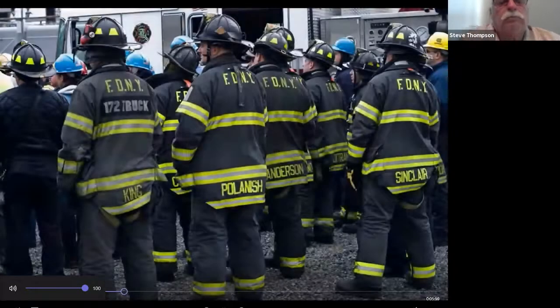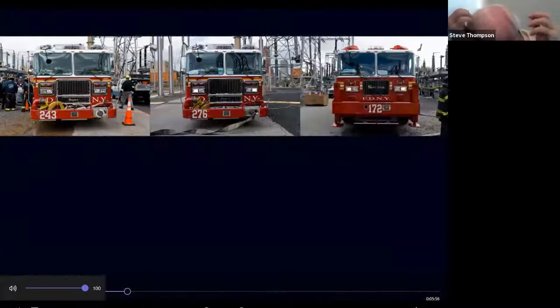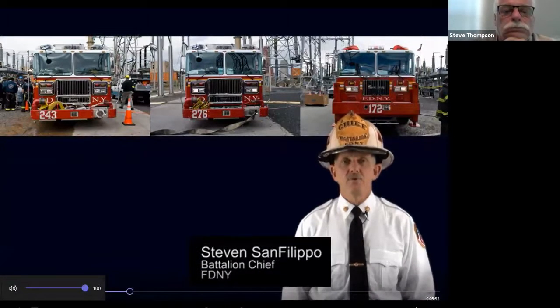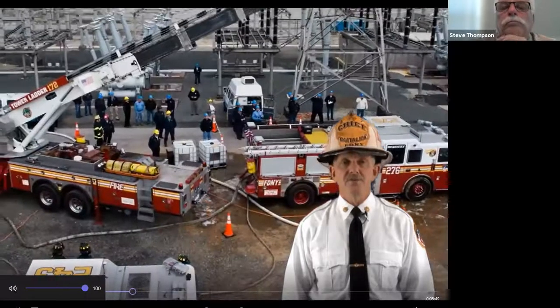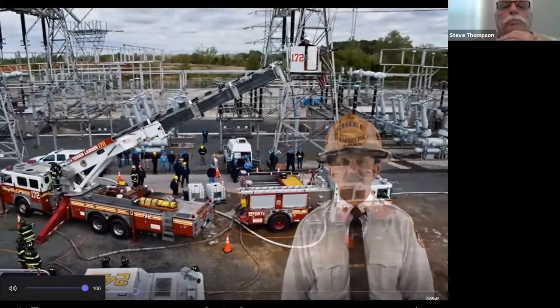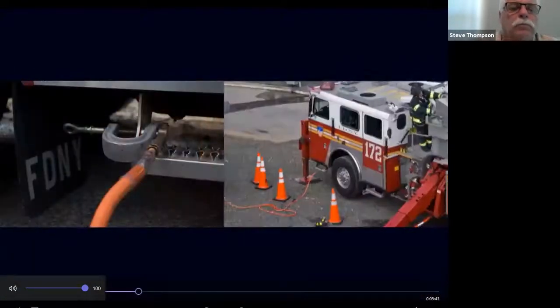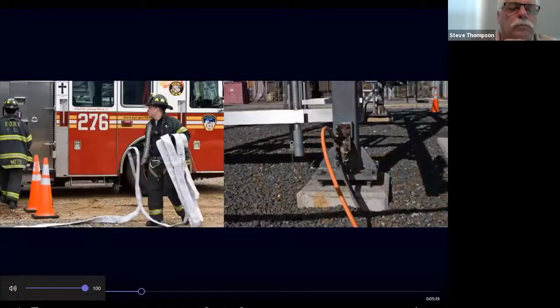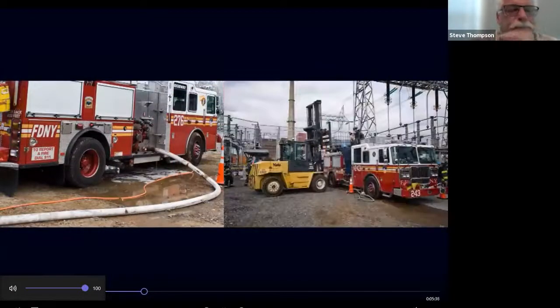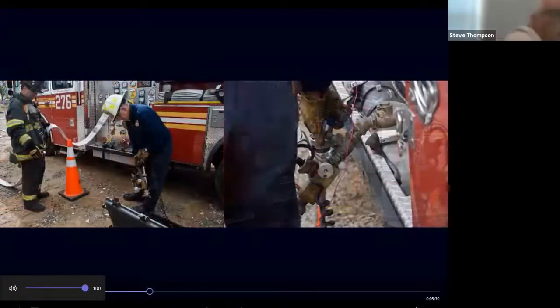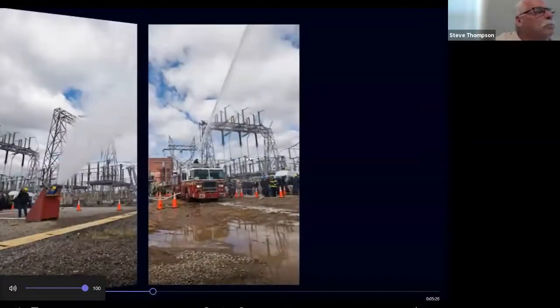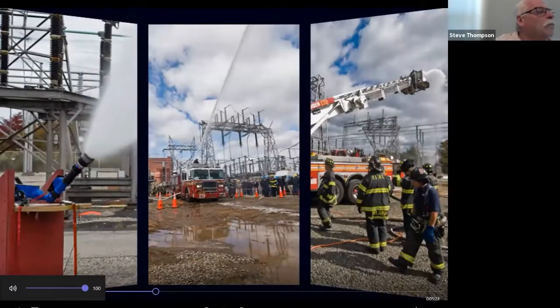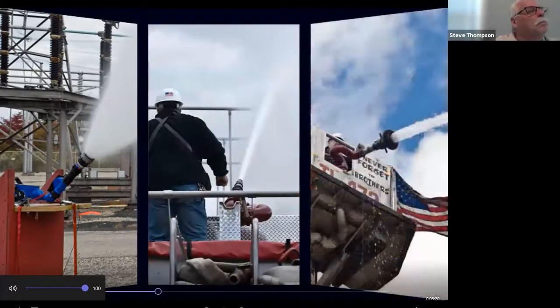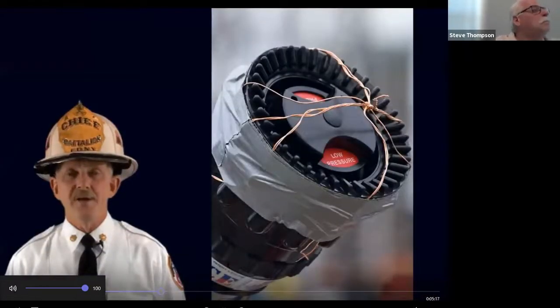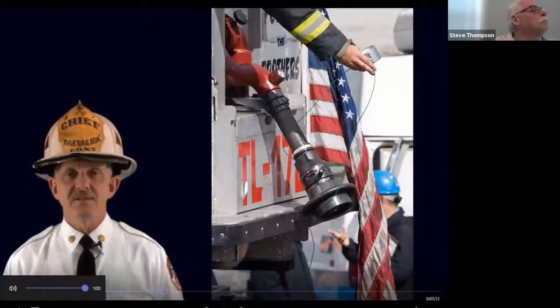For the Con Edison fire suppression test, the FDNY provided 2 pumpers and a tower ladder. Hello, my name is Battalion Chief Steven Sanfilippo. All 3 were used to apply F500 fire suppression agent to the live bus at Con Ed's high voltage station in Staten Island. All our equipment was grounded before any testing commenced. 1 pumper was on a hydrant taking in water and also supplied water to an additional pumper which had F500 concentrate in their booster tank. We mixed it to a proportionate and then used the 3 means of delivery. We used a fixed mounted multiversal nozzle at ground level, a deck gun, and a tower ladder. The nozzles were wired up to measure any residual voltage at these various distances and spray patterns.